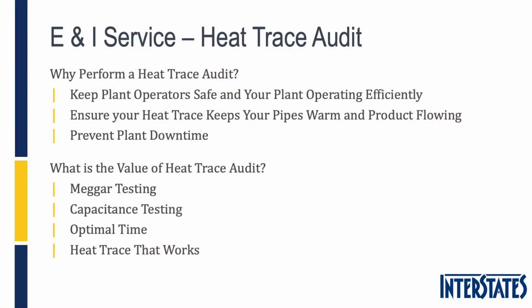Some of the common E&I services that are also performed are heat trace audits. Heat trace is a device that keeps your pipes warm in the winter. It prevents your pipes from freezing up and busting, or just freezing up and your plant going down. Those circumstances can be avoided by checking your heat trace in the summer, maybe even in the fall, before the cold weather comes. Heat trace checks are best done by doing a MEG test to make sure that the heat trace is not shorting to ground, doing voltage and amp checks to make sure that the proper amount of electricity is flowing through the heat trace, and also doing capacitance checks to ensure that the heat trace is providing a reading that's accurate for how long the heat trace actually is installed on the pipe.